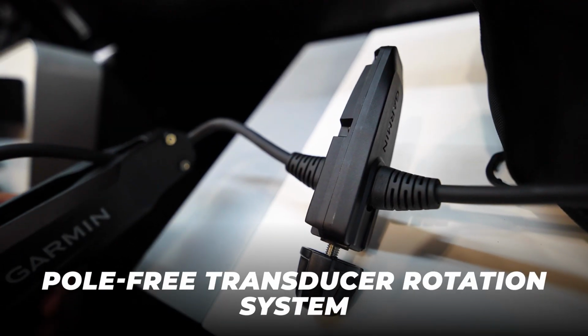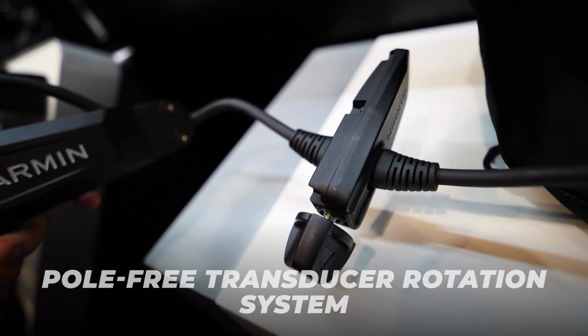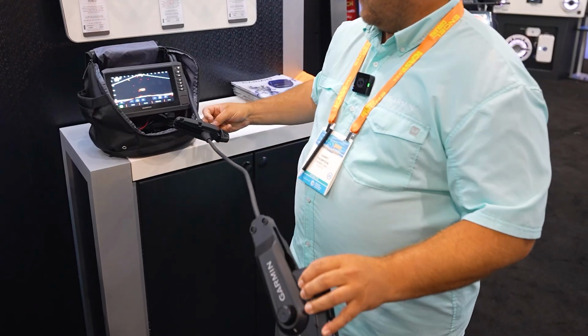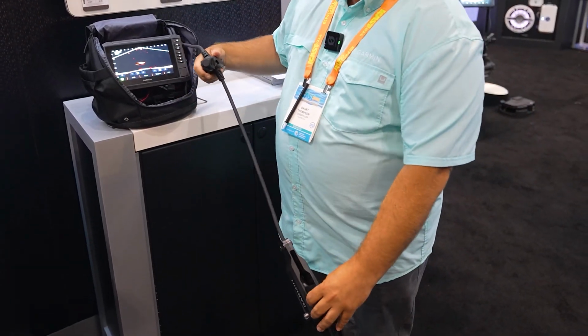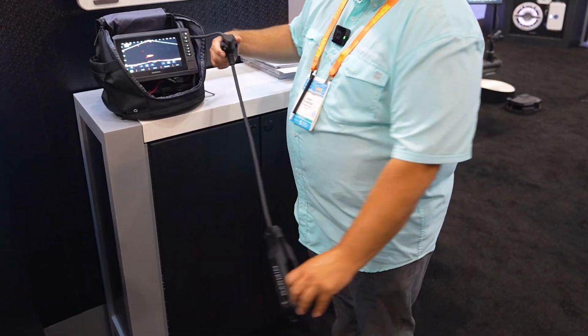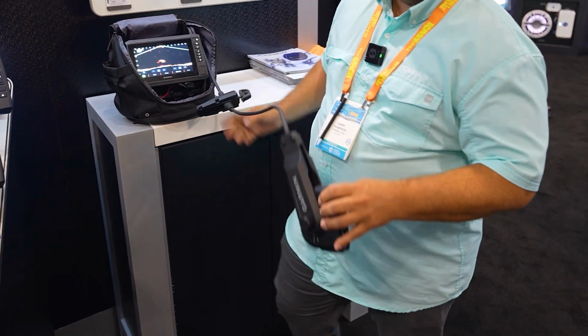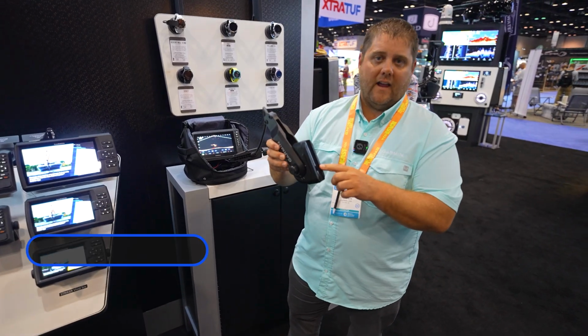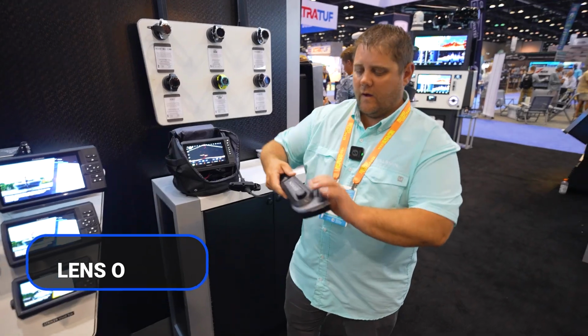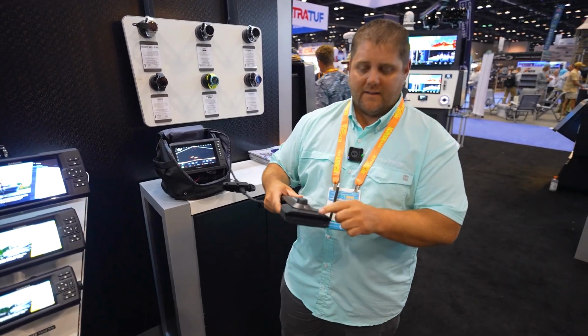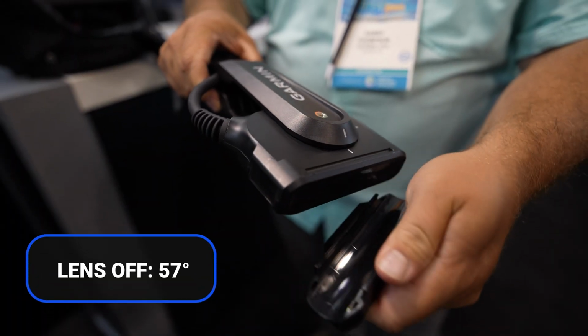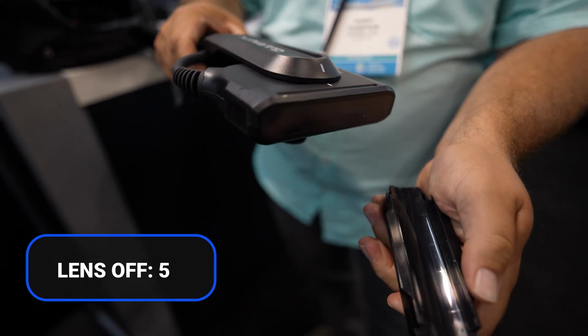We've got a turn handle that works with the transducer here, so if we line it up, and when we're in the forward mode, wherever I point this handle is where my transducer is going to point, allowing us to have forward mode with the lens on at 12 degrees. If I go ahead and go to the down mode and I take the lens off, I'm now at 57 degrees. And that's where this unit really excels.